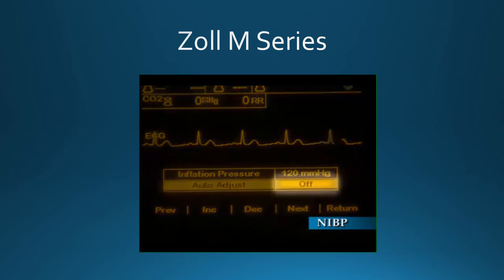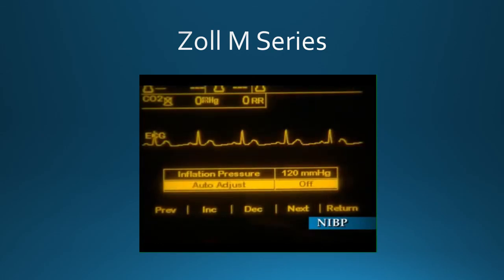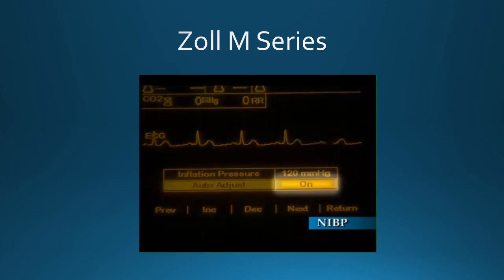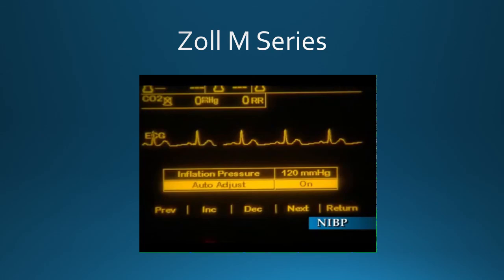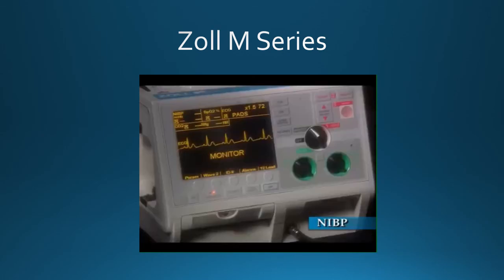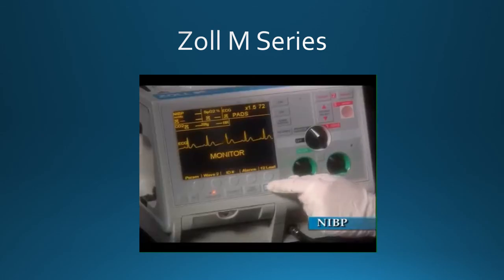If the auto feature is set to off, the selected cuff inflation pressure is used for all measurements. If the auto feature is set to on, the selected cuff inflation pressure is used for only the first measurement. After the first measurement, the cuff inflation pressure automatically adjusts to 30 millimeters mercury greater than the systolic value of the previous measurement. To take a single measurement, press the NIBP button.